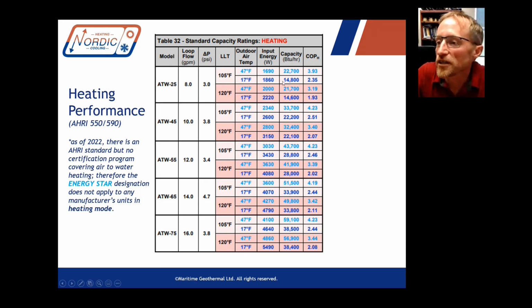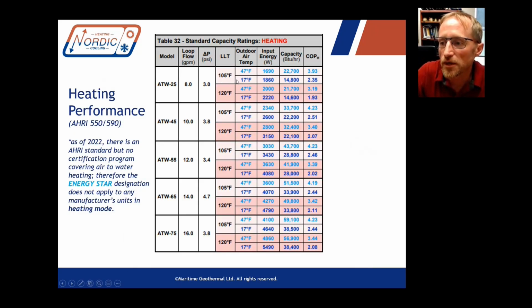These are some standard conditions, and the table shows the output and the COP at two different indoor water temperatures, 105 and 120. For each of those, there are two outdoor temperatures, which are standard rating conditions. I don't have a picture of it here, but there's also a detailed performance table with many more outdoor temperatures on it. If you're curious how much this heat pump is going to put out at a given outdoor temperature, you can look at those tables, which, as I say, are in the manuals.